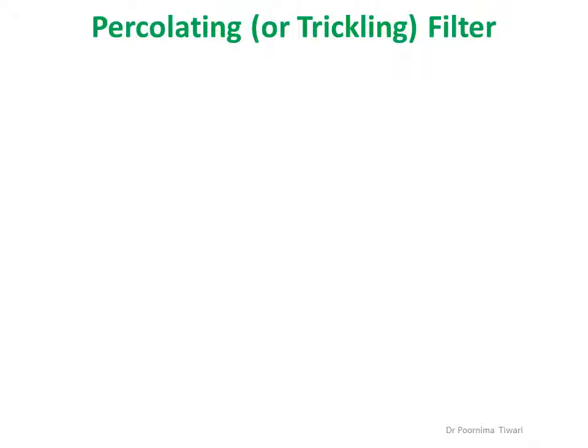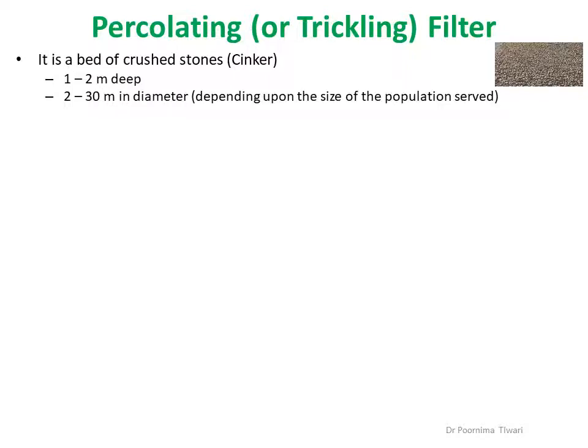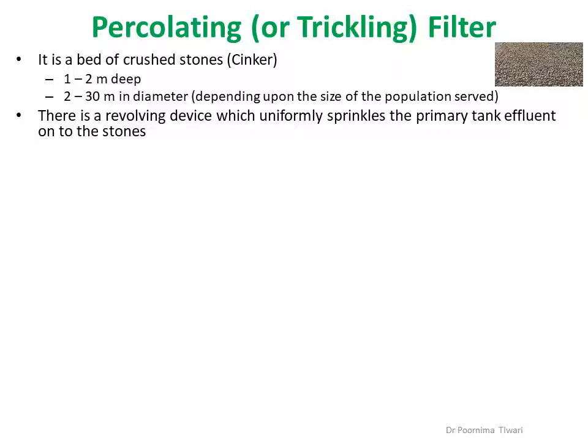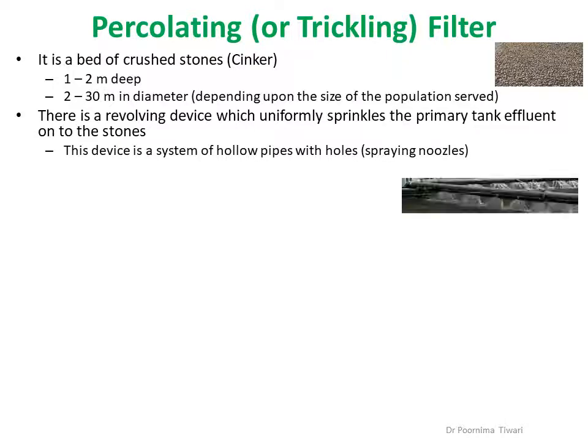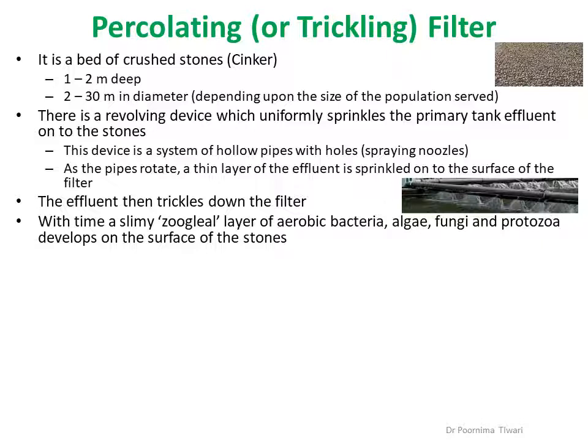The two methods of aerobic oxidation: the first is the percolating filter, or trickling filter. A percolating filter is a bed of crushed stones around 1–2 meters deep, with diameter depending on the population to be served. A revolving device uniformly sprinkles the primary tank effluent onto the stones — a system of hollow pipes with holes through which sewage is sprayed onto the surface of the bed. As the pipes rotate, a thin layer of effluent is sprinkled onto the filter surface and then trickles down. A zoogloeal layer forms on the surface of the stones, consisting of aerobic bacteria, algae, fungi, and protozoa.